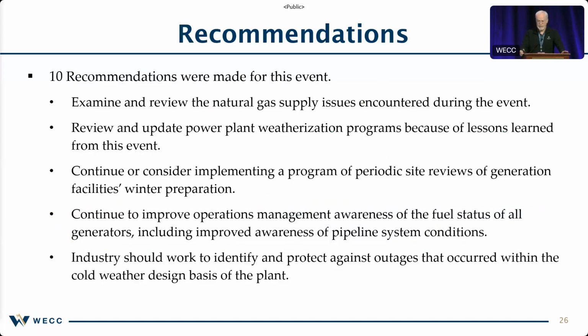Ten recommendations were made for this event. They were going to look at the natural gas supply issues that were encountered during the event. They were going to look at power plant weatherization programs. They were going to look at site reviews of generation facilities' winter preparation. All of these may sound similar to some standards that are in place or coming up. They're going to look at improving awareness of pipeline system conditions, because what they recognized in the gas-electric interdependency is that there wasn't a lot of communication or understanding between the two.